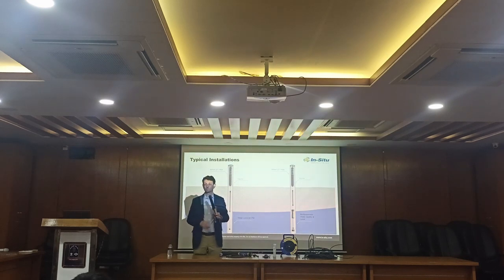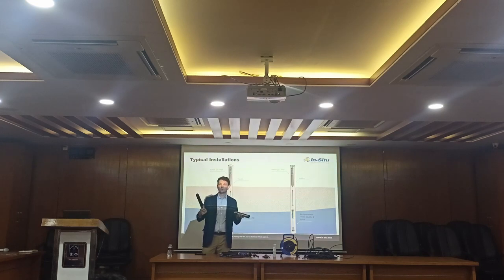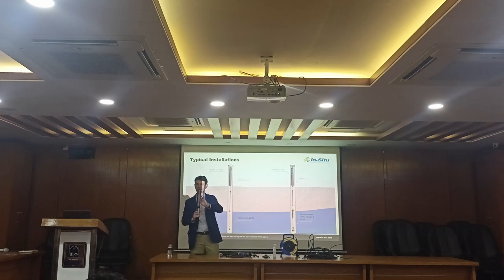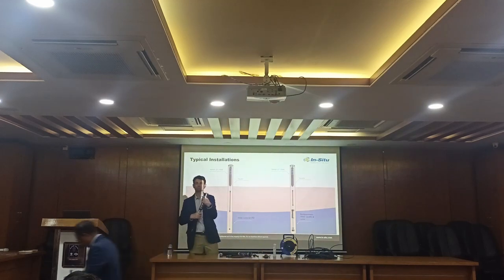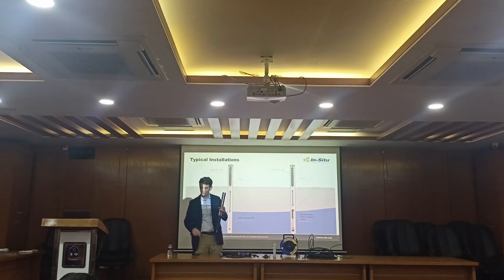With the app, there's a thing that says calibration. Click calibration, and it gives you pictures showing exactly what you need to do with the instrumentation to complete the calibration—everything from taking the restrictor off, flipping it over, putting it on, entering calibration mode, so you have a place to put your standard solution, and then it walks you through the whole setup process. At that point, all you need to do is look at your phone, hit a button, and wait. That's it.